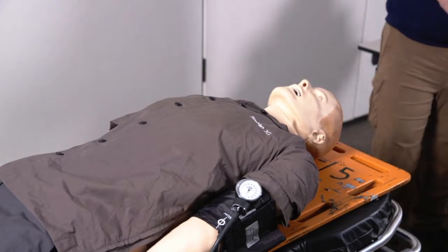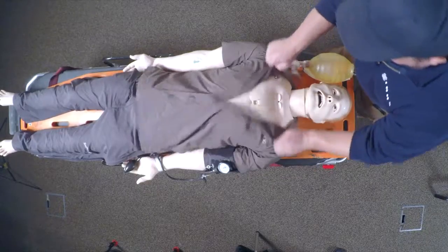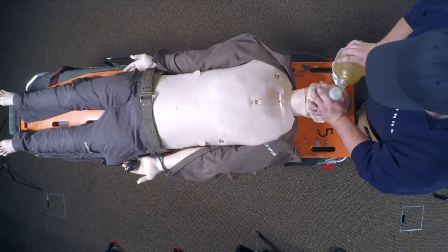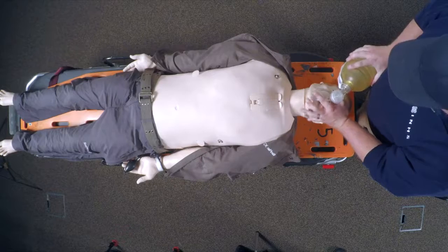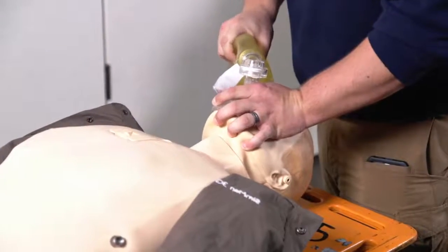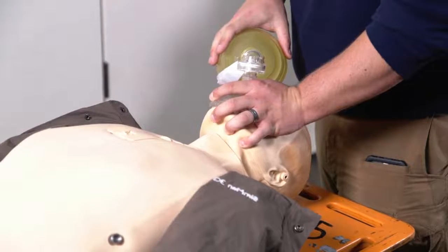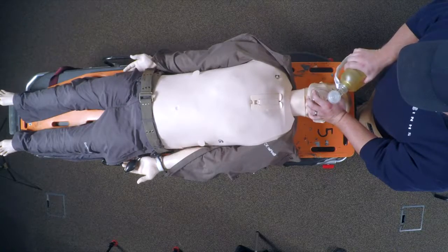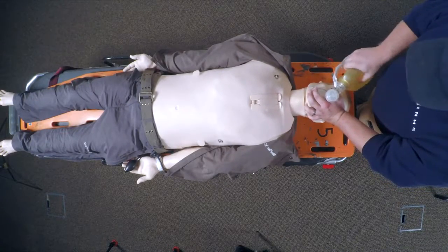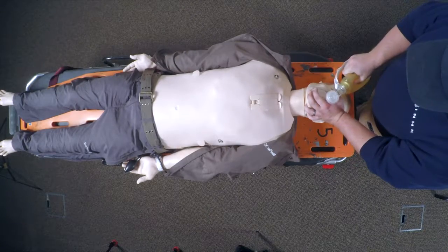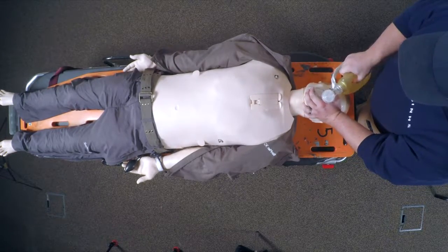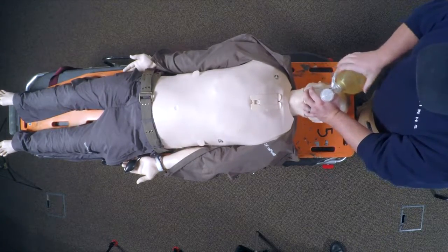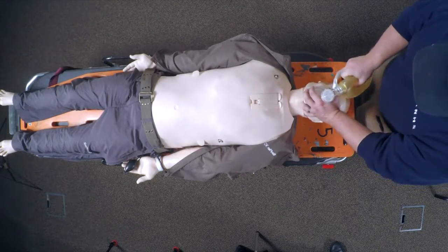If Sim Man stops breathing or needs assistance with ventilation, we can actually take the BVM, bag our patient, and he'll simulate those ventilations, and we can pick up how good of ventilations you're doing, the timing and rate that you're doing on your ventilations, and if you overventilate, he will actually get stomach distension as well, which you'll be able to see. As you can see, his stomach is rising and getting distended if we overventilate.